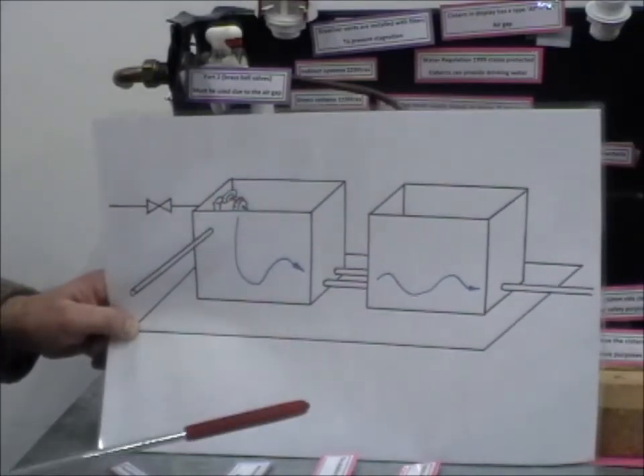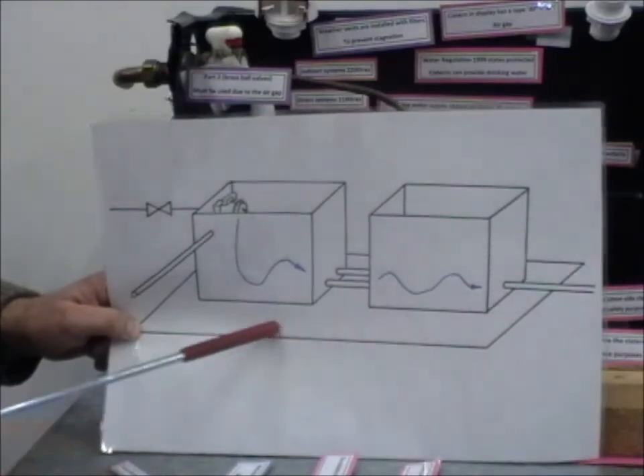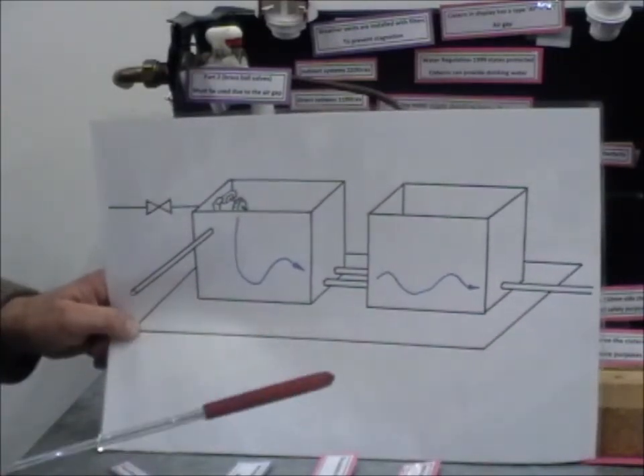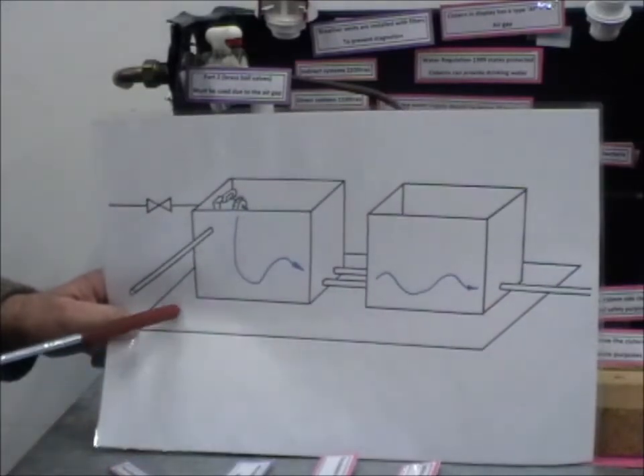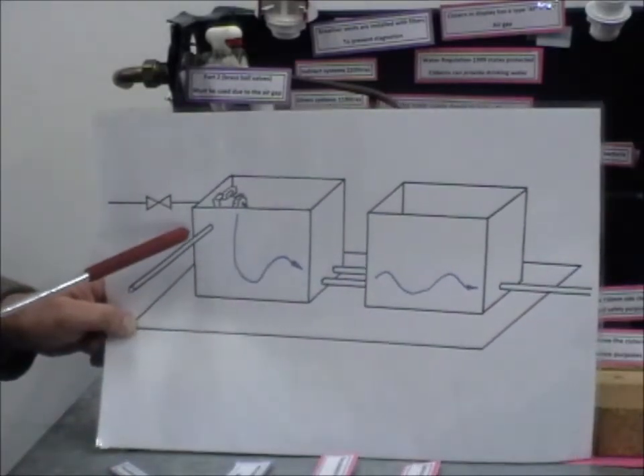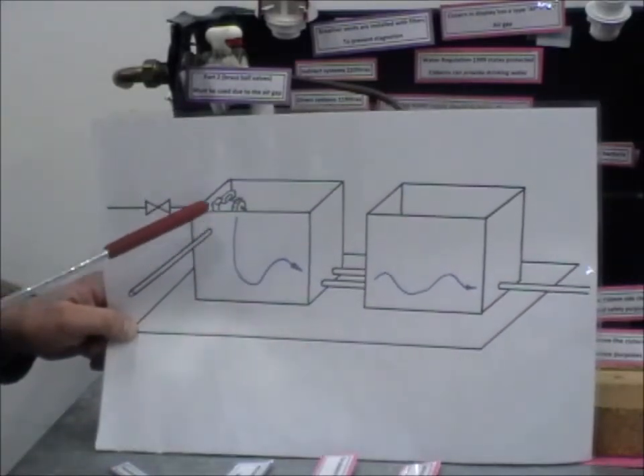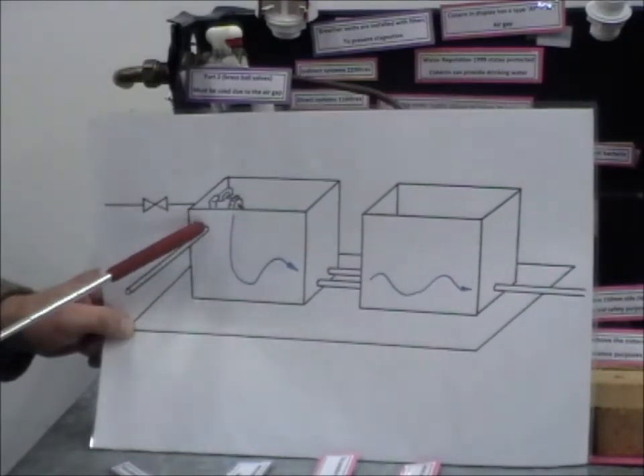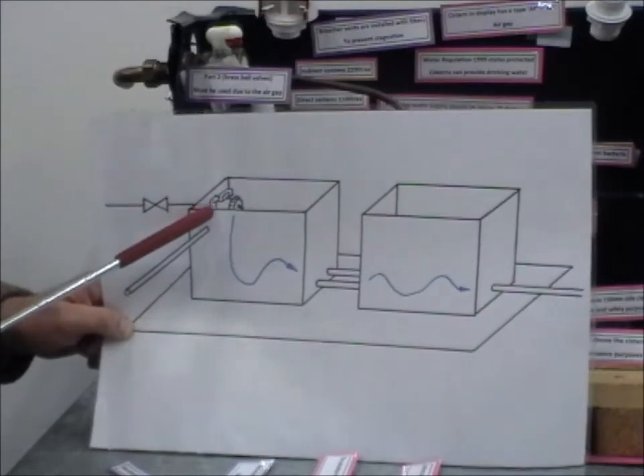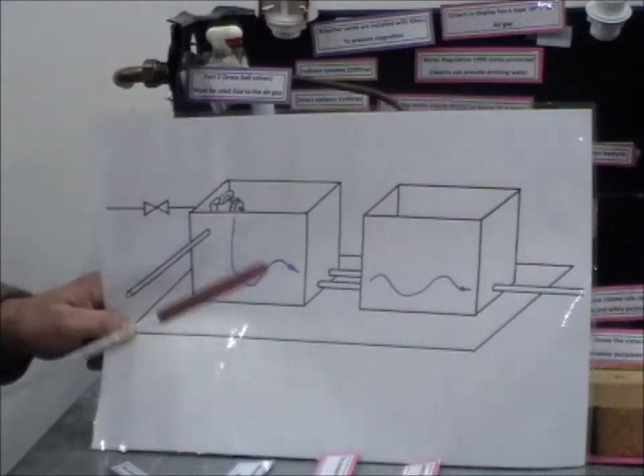Isolation valve to the ball valve. You've got a base, that should be plywood, firm, supporting the whole area. Clearance of 150mm around the edges. You've got the overflow pipe, which should be 25mm below the ball valve. 25mm above the water line. The overflow pipe, if you're lucky, is in the same cistern as the ball valve.